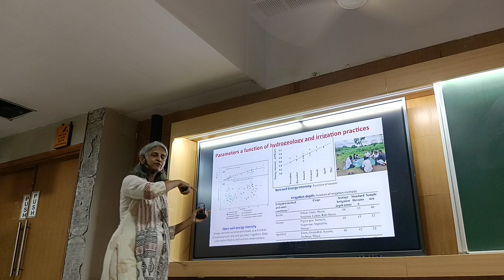No, failure is different from borewell depth. Why does pump failure happen? It can happen for many reasons, but one is that when low voltage is supplied to pumps, they draw very high current, which heats up the wires and the insulation, and that's why the pump fails and has to be rewound. So it has nothing to do with borewell depth as such. Does that answer your question?